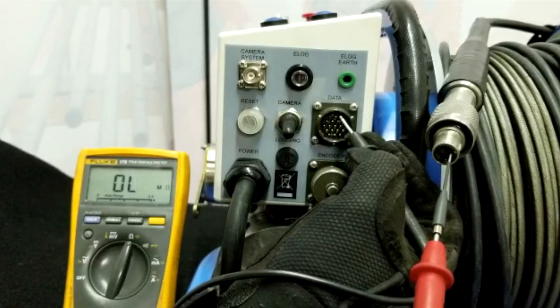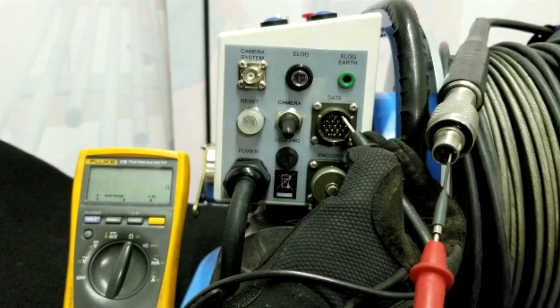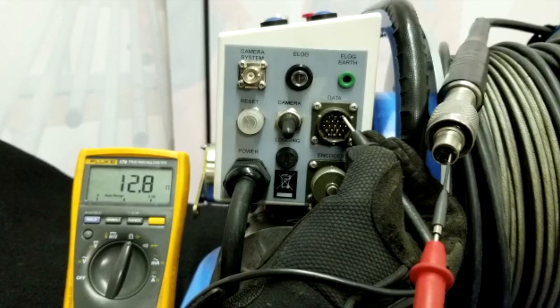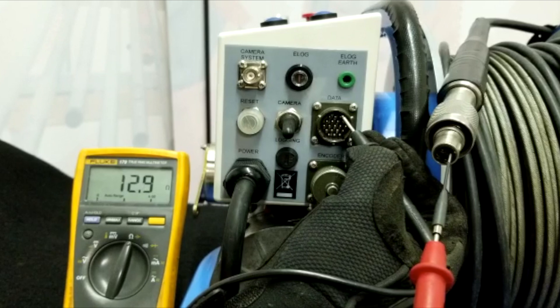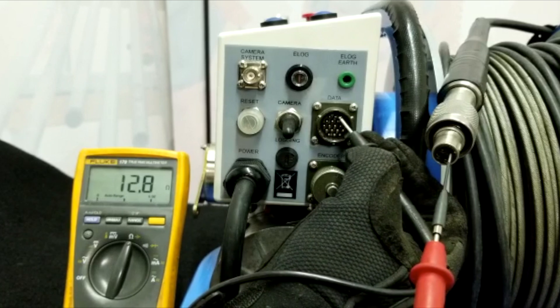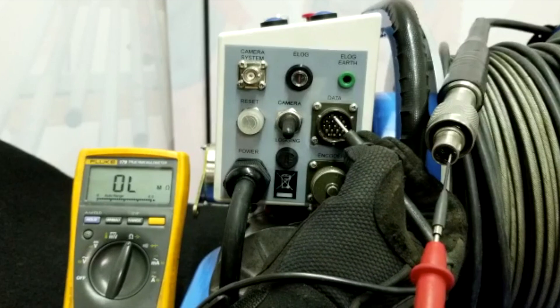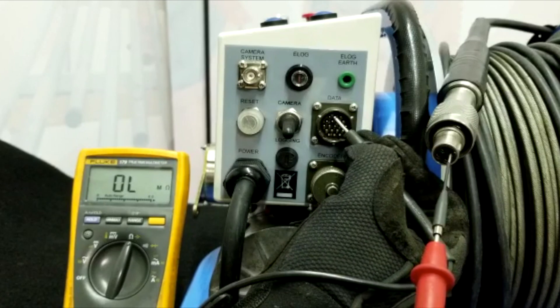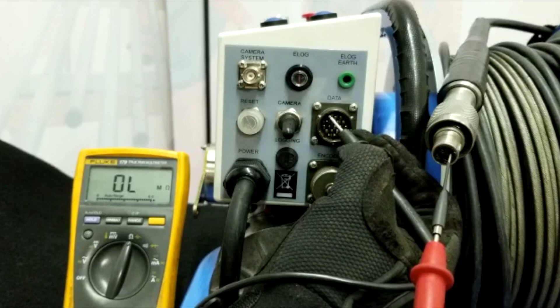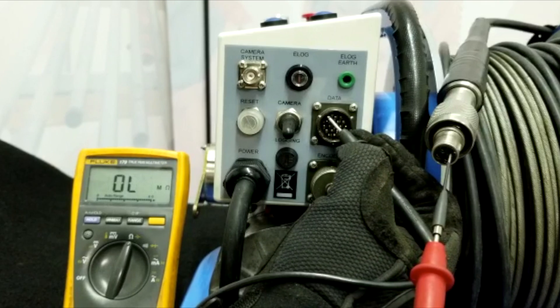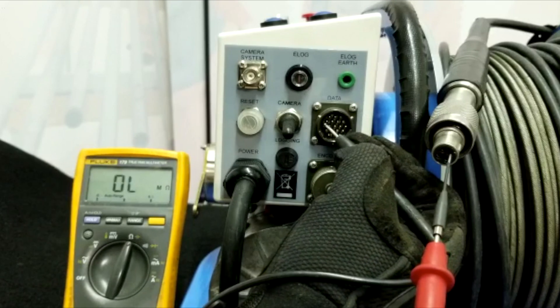And we're gonna check against our pin B as in Bravo. There you go, you see that, 12.98. Alright, and if I check the next one, that's pin A as in Alpha, it's nothing. Pin M as in Mike, we have nothing. Pin L as in Lima, nothing. Pin K as in Kilo, nothing. So good, good, good.